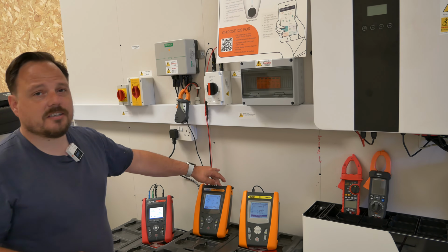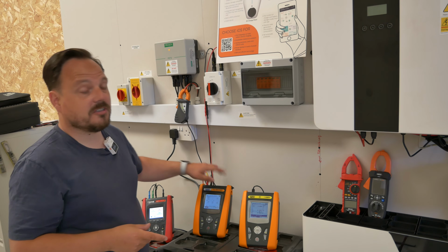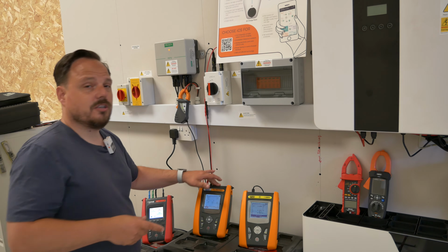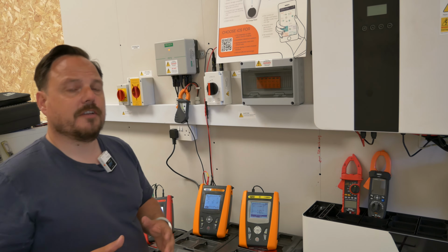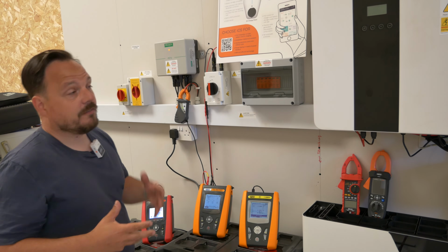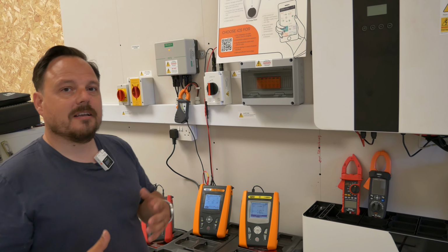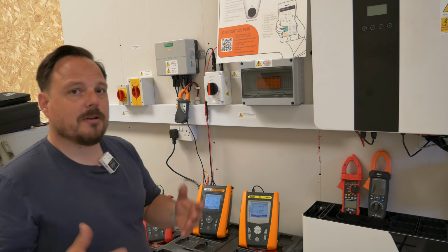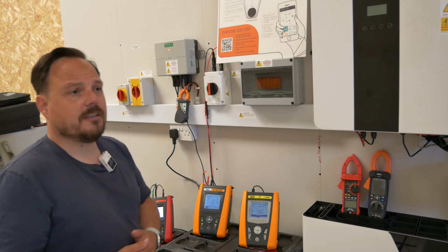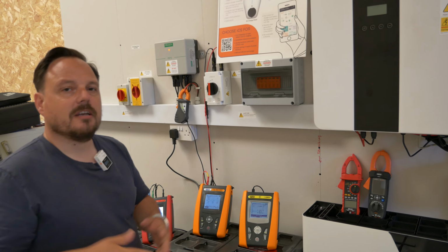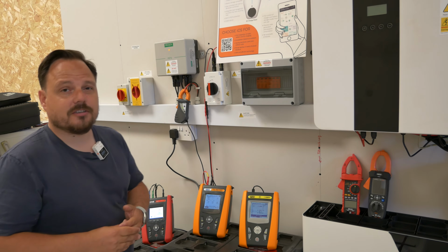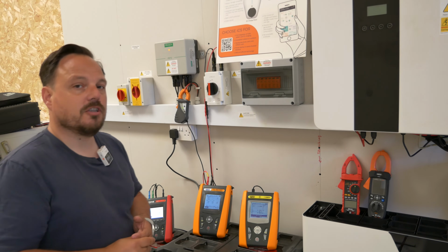This is the ISA test. For those who watched some of the short form content, you'll have seen this already. It can do IR testing while there's up to 1500 volts present, which with solar systems is likely, maybe not quite 1500 volts, but often into the 500-600 volt region, and it can still carry out an insulation resistance test with that voltage present.